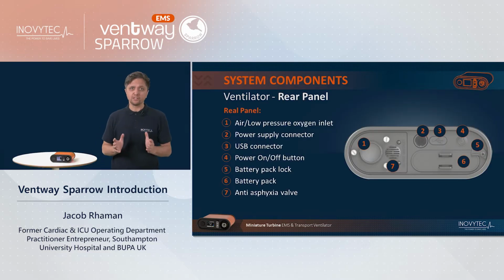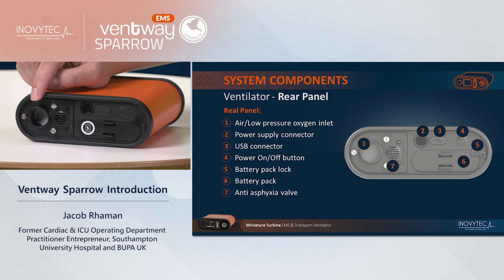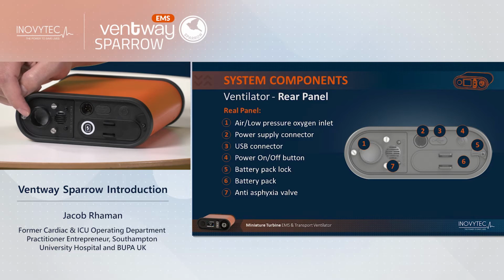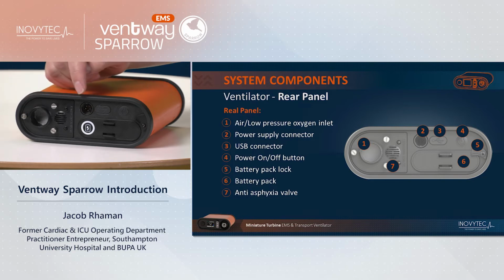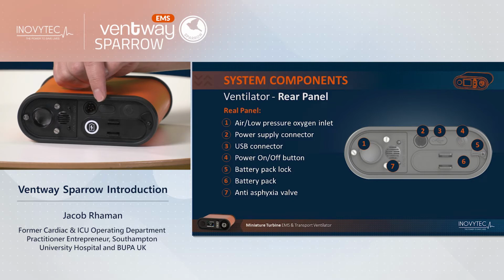On the rear of the device, there are 7 different components. 1. Air or low pressure oxygen inlet. Situated behind this is the filter, which must be replaced after every 300 hours of use. The Ventway Sparrow will give a notification to the user that the filter needs to be replaced. 2. The power supply, which also charges the battery. 3. The USB port. This can be used for downloading of information on usage and for technical service information.